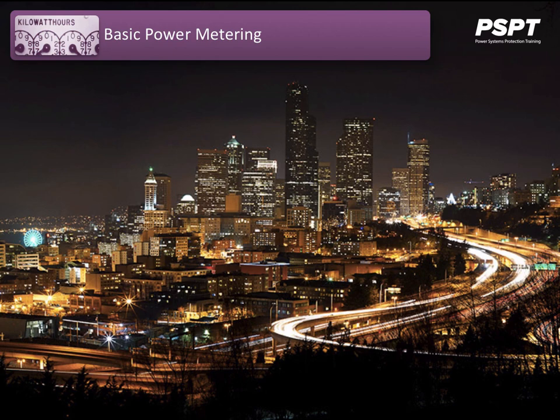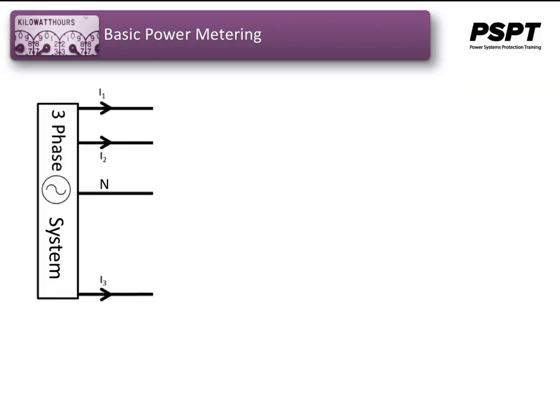So what we're going to see in the next few installations is some approximations that are made that are acceptable from a billing standard, such that the cost will be kept down, and we'll be trying to reduce the number of watt meters, or certainly the number of elements in a watt meter, in metering three-phase systems. In a utility's three-phase system, often referred to as an infinite bus, because utilities tend to be very large and they're interconnected with each other, the infinite bus refers to the fact that the voltages, regardless of the loads, remain relatively unchanged. In other words, they are going to be equal and 120 degrees apart just about at all times.